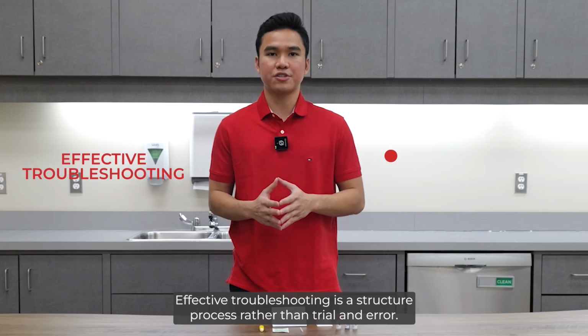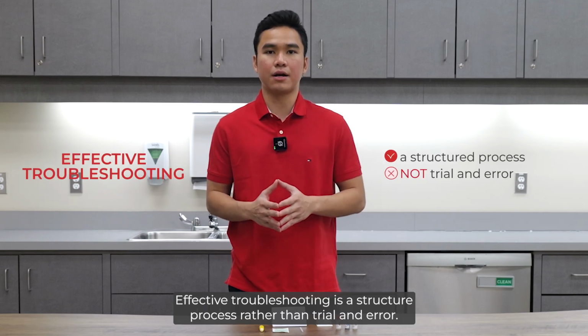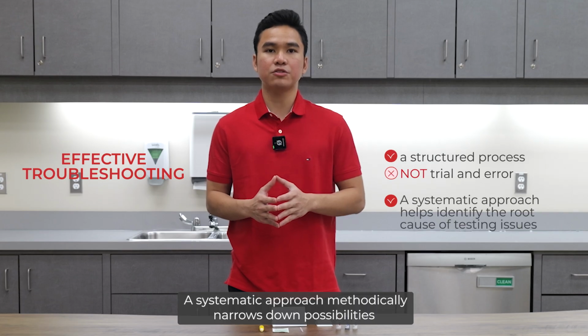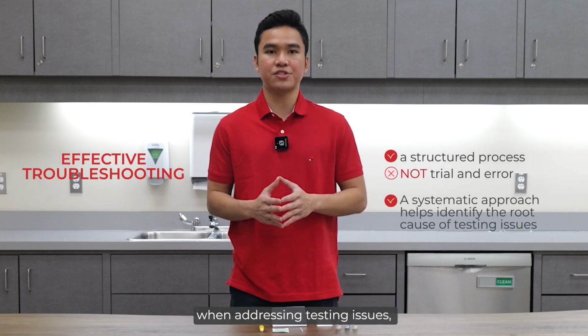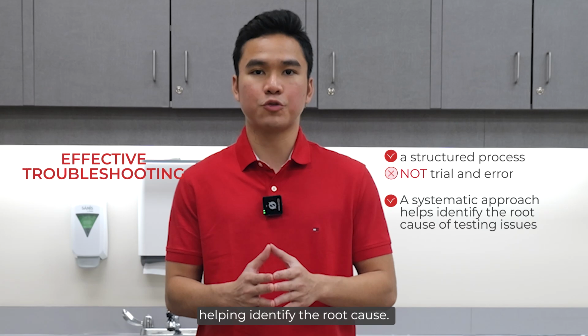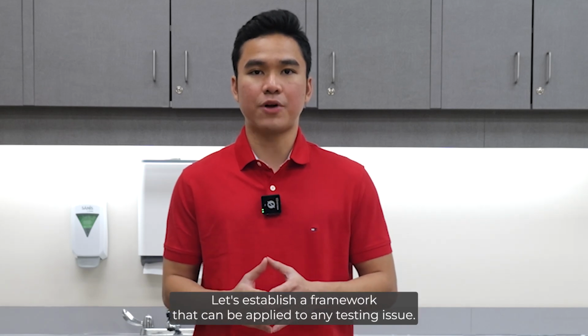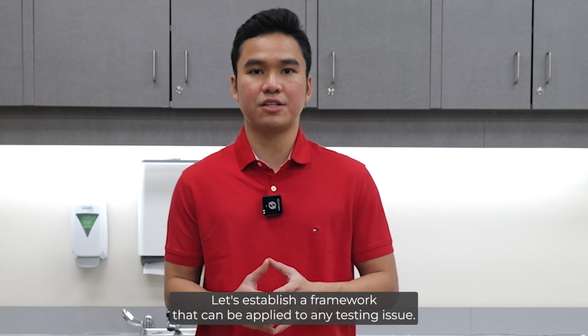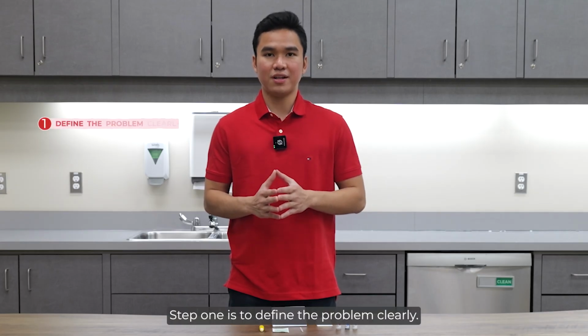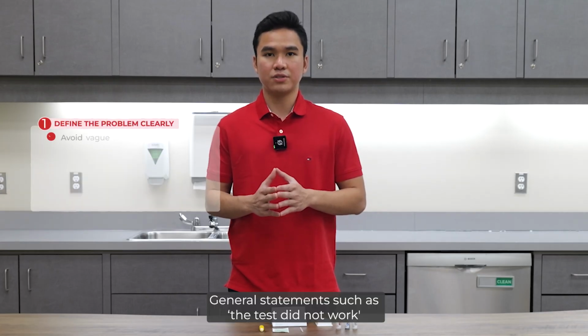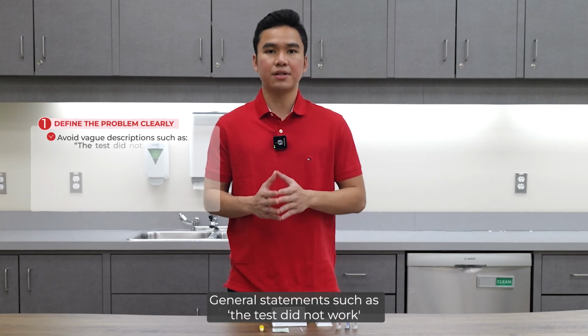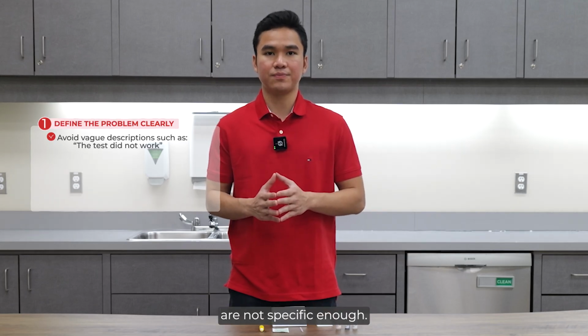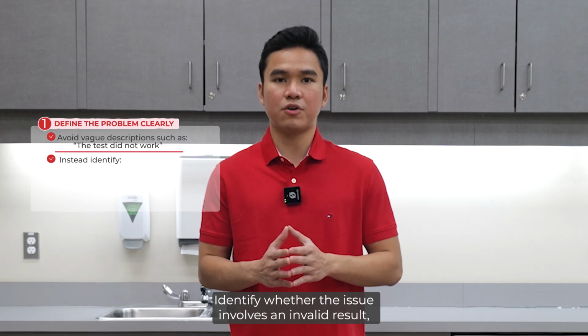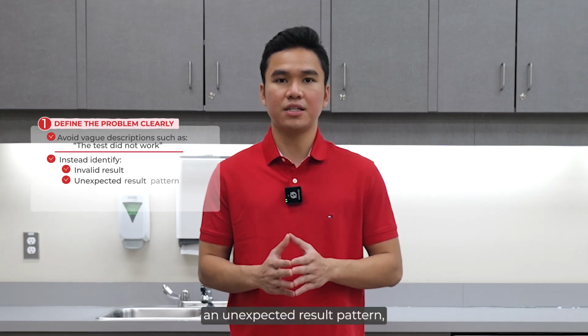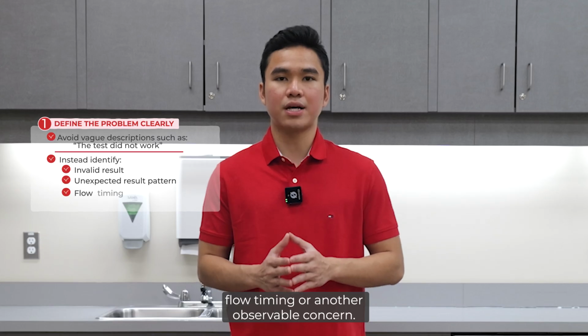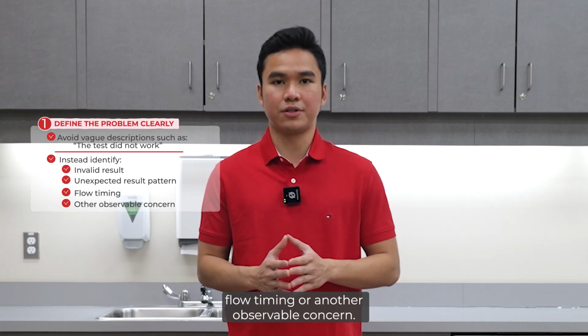Effective troubleshooting is a structured process rather than trial and error. A systematic approach narrows down possibilities when addressing testing issues, helping identify the root cause. Let's establish a framework that can be applied to any testing issue. Step 1 is to define the problem clearly. General statements such as, "The test did not work," are not specific enough. Identify whether the issue involves an invalid result, an unexpected result pattern, flow timing, or another observable concern.